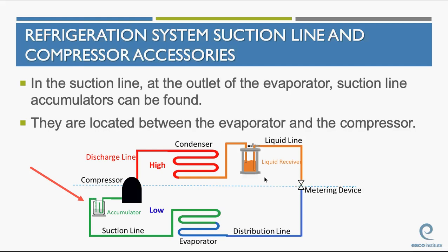In the suction line, at the outlet of the evaporator, there's a suction line accumulator. I showed you this on another diagram. They're located between the evaporator and the compressor. The suction line accumulator has one purpose in life, and that's to make sure that there's no liquid refrigerant going to the compressor. The liquid falls to the bottom of it, and we pull the suction gases from the top of it. All it does is ensure that there's no liquid refrigerant going to the compressor. But it does hold refrigerant, so you have to be aware of this when you're recovering.